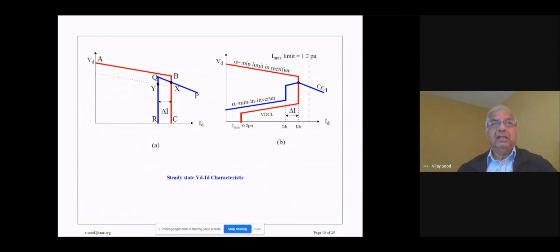And this way, if the operating point is at Y, you can see now the inverter will take over current control, and the rectifier will be on this dotted line over here, which is the alpha min characteristic of the rectifier. So that will take over the voltage control. This way, the control strategy will be changed, but you can still operate the system at almost 0.9 per unit current and almost at full voltage. This could be a change in the voltage by 10% or so.